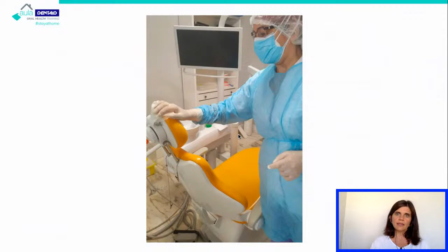And after, we will take all the material and follow all the steps one by one. We will collect the material. We will make a pre-wash or decontamination of the material. If we are going to sterilize it immediately, it's very important to use, for example, a wet disinfectant or an enzymatic disinfection. We will use a manual or mechanical cleaning. If we use a manual one, as you know, you have to rinse and dry. If you use an ultrasound, the more you can mechanize in the sterilization process, the better.